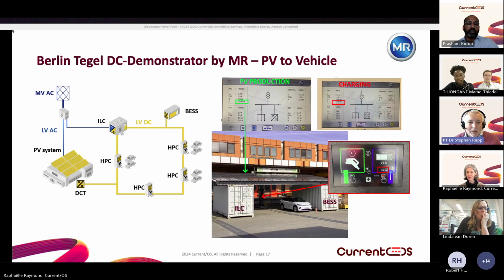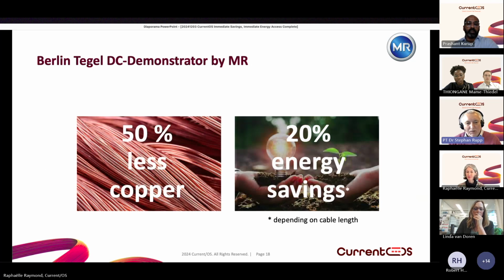If we go to the next slide, we also get the same amount of copper savings, which is a quite simple computation. On a DC system, you just need 2 conductors, in comparison to the 3 conductors you would need for an AC system. So there's always 1/3 of copper savings. If you manage to increase the voltage a bit above the usual low voltage AC level, then the currents are getting still smaller and you are saving some extra copper. That's the reason behind the copper savings.